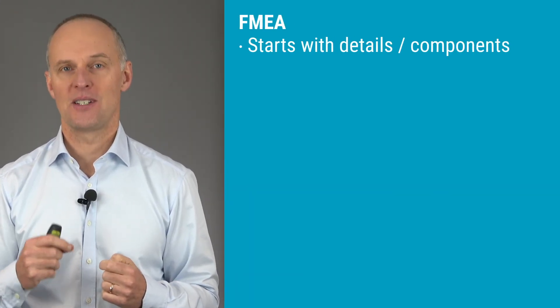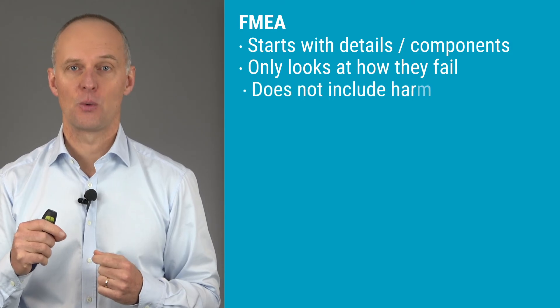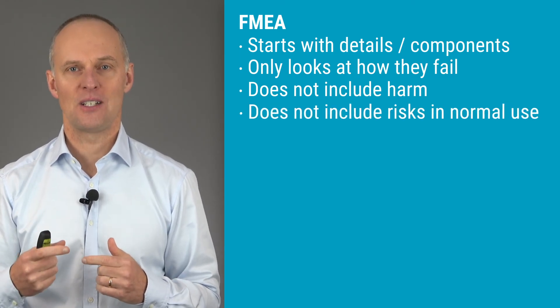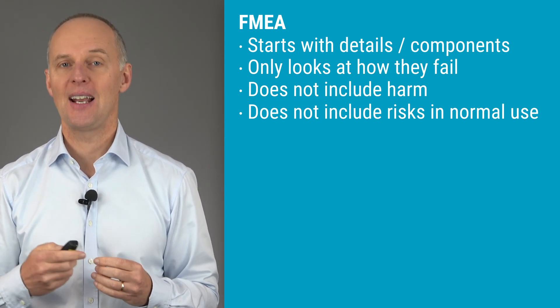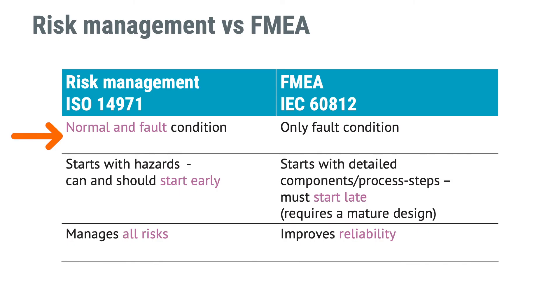Having looked at these examples, you may have noticed that FMEA starts with details or components — you look at how specific components or process steps could fail, and there was no mention of harm in this FMEA. And since we've only looked at failures, risks relating to normal use have not been included. Let's compare this with ISO 14971 risk management and highlight some of the major differences. FMEA will only consider risks arising from fault conditions, and since it starts with component or process step failures, by definition it won't be possible to start until the design or production processes are fairly well known — meaning in a late stage.